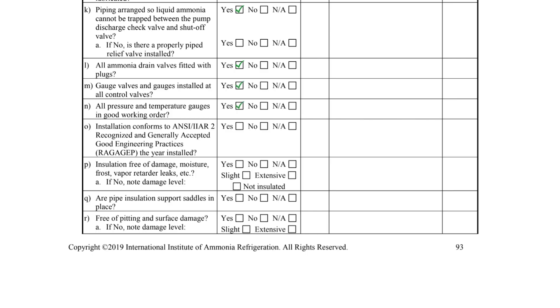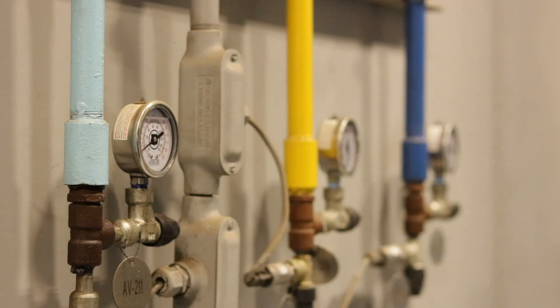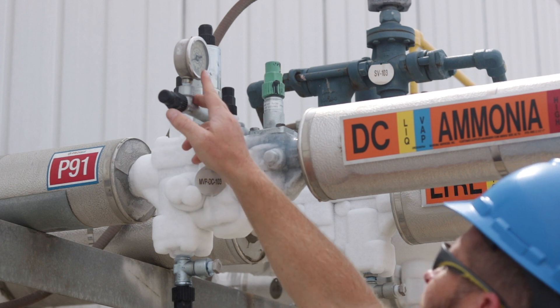Items M and N ask if gauge valves and gauges have been installed at all control valves and whether all of the pressure and temperature gauges are in good working order. Roof-mounted gauges can be damaged by the sun, rendering it difficult to decipher the gauge reading.